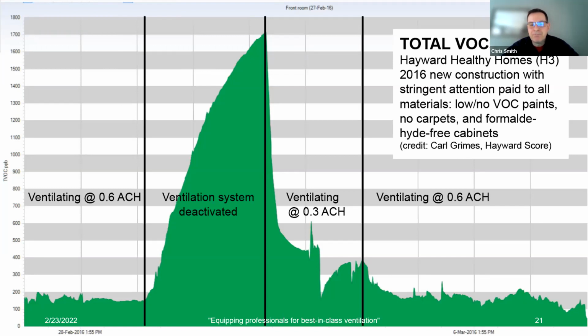And then later on in day 5, they ramped the ventilation rate back up to that 2/3 air changes per hour, and we see the VOC rate steady or level out again, more or less. So just an example of what happens, how air quality is impacted by ventilation and the ventilation rate.